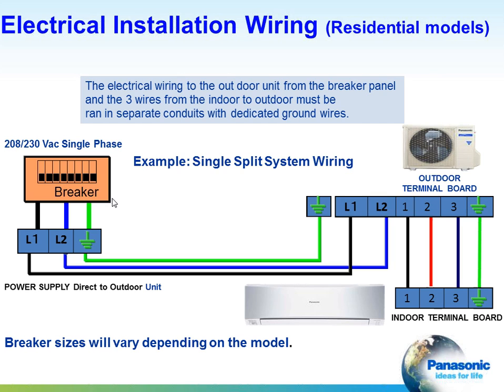Electrical wiring is fairly simple with this. We're going to bring from the breaker, we're going to use AWG12, and we'd like to see you use stranded wire. That gives us better continuity in the electrical wiring, and the reason that we want that will be covered in the wiring between the outdoor unit and the indoor unit.